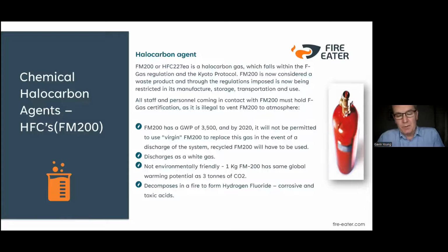So since 2016, the global warming potential of FM200 became an issue. So it's been phased down, which essentially means being phased out, because it's not going in as a new product. It's only being replaced. It discharges as a white gas. It's not environmentally friendly. 1 kilogram of FM200 has the same global warming potential as 3 tons of CO2. When you have a fire, it decomposes into a form of hydrogen fluoride, which is corrosive and emits toxic gases. So it's not a very pleasant place to be when the system discharges inside a room.